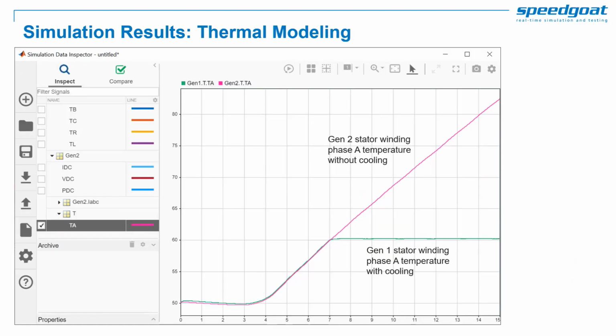Here we see the thermal response of phase A stator winding in both generator 1 and generator 2. Only generator 1 has active cooling, so we can see the difference in the response and confirm that the active cooling circuit is functioning as expected. In this case, the active cooling circuit is configured to regulate temperature to 60 degrees Celsius. For the purpose of this demo, we have parameterized the system to show a thermal response in only a few seconds of simulation time.